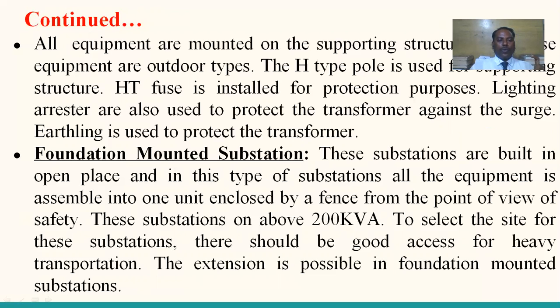The pole mounted substation. Similarly, foundation mounted substation we can observe. In foundation mounted substations, a concrete beam, generally observed on the roadside, a strong concrete beam is to be constructed. On the beam, the transformer is to be installed. So these substations are built in open place, and in this type of substations, all the equipment is assembled into one unit enclosed by a fence from the point of view of safety.